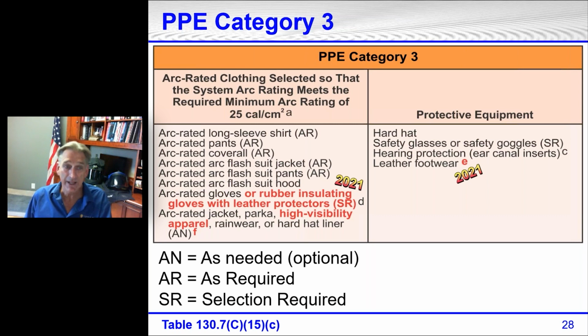We are on the right side. It did say arc-rated gloves, rubber insulating gloves with leather protectors, selection required. That's the same as what it was, although those words weren't in that table before. High visibility apparel was added to the table. There was a footnote F added to this table, which we'll look at near the end of this webinar in a few minutes.